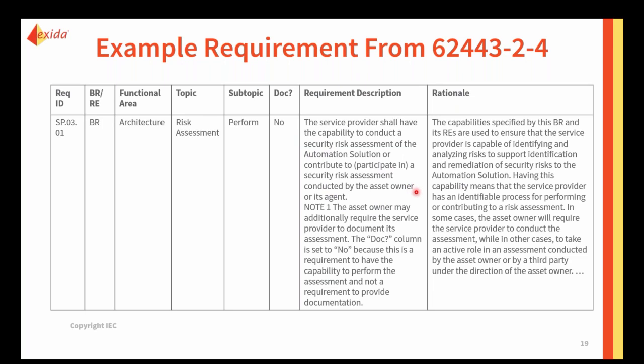of a sentence format. As we can read from this example requirement from 2-4, it says that the service provider shall have the capability to conduct a security risk assessment of the automation solution or contribute to, in parentheses, participate in, a security risk assessment conducted by the asset owner or its agent. Essentially what this is saying is when you're the service provider for an automation solution, you need to either be able to go through and conduct a cyber risk assessment on that portion, or if the asset owner chooses to complete that risk assessment, you have to be able to then provide input.